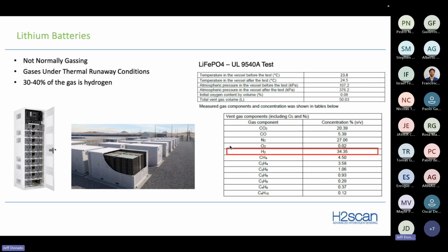So lithium batteries, of course, are not normally gassing. We know they only gas under thermal runaway conditions. But this is a UL 9540A test report that I pulled for this particular battery type. And as you can see, hydrogen is one of the most prominent gases that actually come out of a lithium battery.